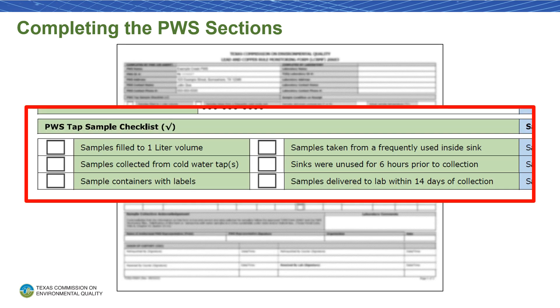Next, let's go through the tap sample checklist. Mark whether your samples were filled to the one-liter volume, whether they were collected from cold water taps, whether the sample containers have labels, whether the samples were taken from frequently used inside sinks, whether those sinks were unused for six hours prior to sample collection, and whether the samples were delivered to the lab within 14 days of collection. Please be aware that samples need to meet all of these criteria to be accepted by a lab, and samples that don't may be rejected. Additionally, any lead and copper samples taken from entry points will have different collection procedures and not all PWS tap sample checklist items will apply. Please contact the lead and copper monitoring team for guidance if you have questions regarding entry point lead and copper sampling procedure.